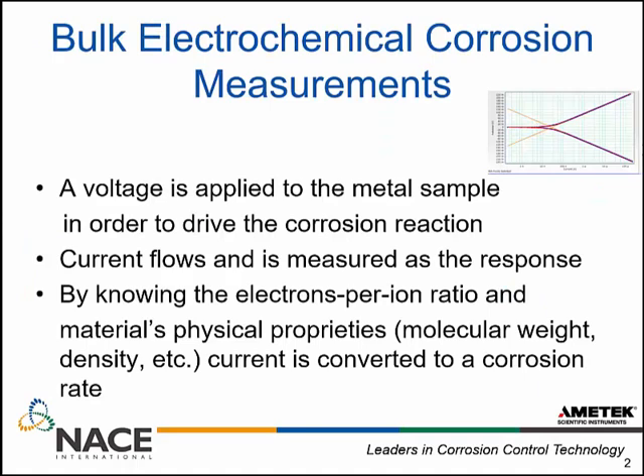First, let's define what we mean by bulk electrochemistry measurements, and then we'll contrast that with local measurements. From an electrochemical corrosion rate measurement study, the typical plot shown here is a Tafel plot in the top right-hand corner. The procedure to generate such a plot is to apply a small voltage to a metal sample and drive the corrosion reaction. The corrosion reaction is an electrochemical reaction that causes current to flow, and our potentiostat measures that current. By knowing physical properties of the materials — such as molecular weight, density, and others — we can convert the electrical current through the potentiostat into a corrosion rate.